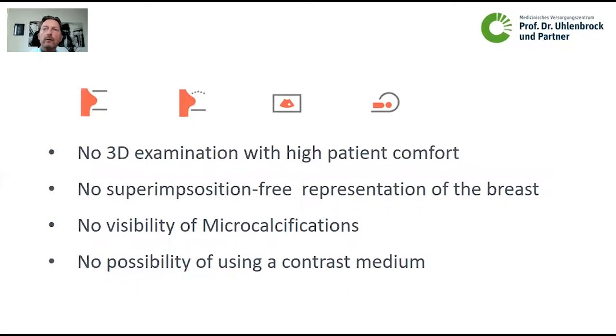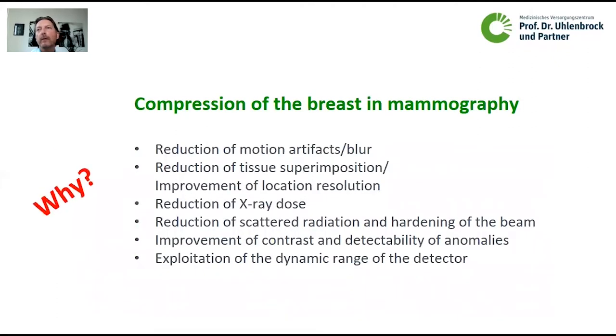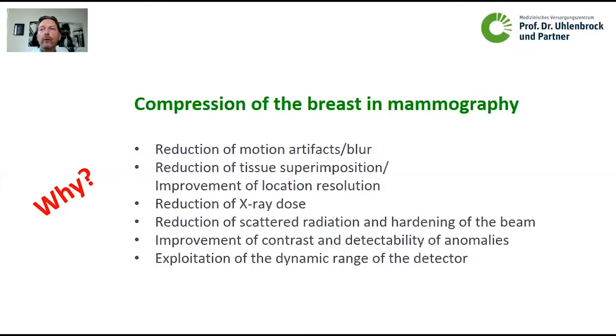But what about comfort? Why do we squeeze the breast? Why do we have to compress in mammography? This is necessary for the reduction of motion artifacts and blurring of images. We also compress for the reduction of x-ray dose, reduction of scattered radiation and beam hardening, improvement of contrast and detectability of anomalies, and exploitation of the dynamic range of the detector. So we have to compress to do good mammography.